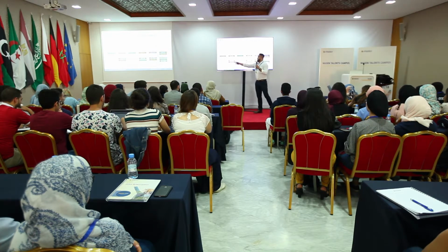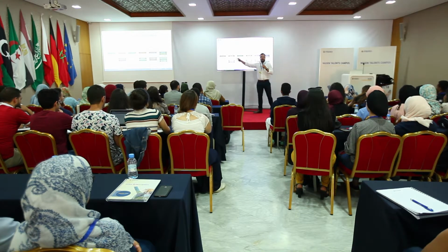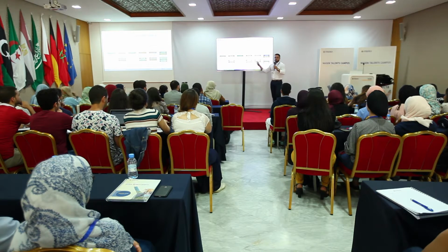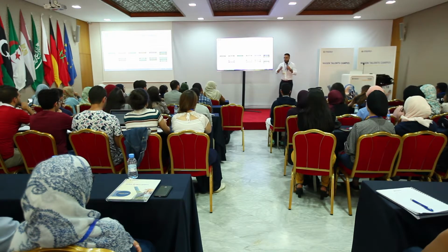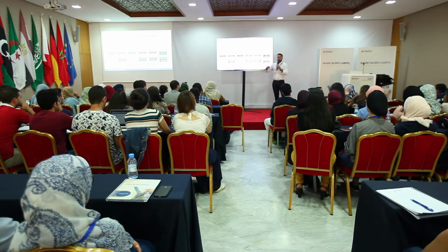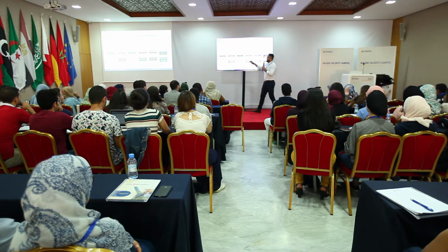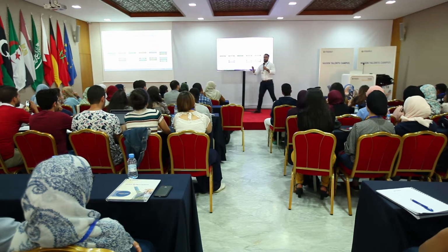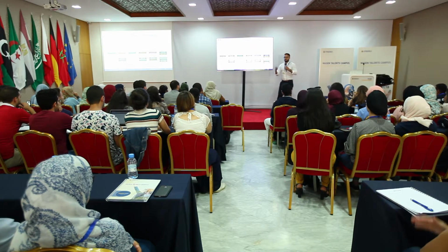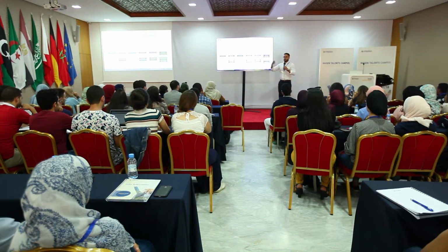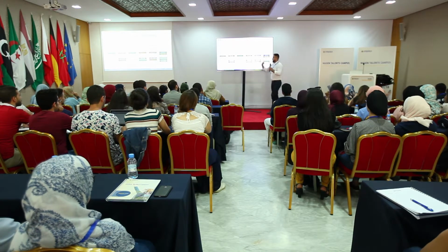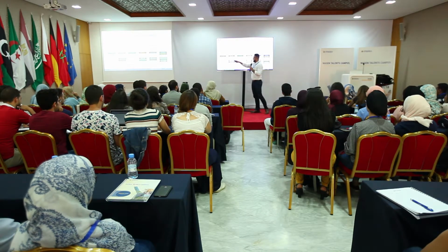because for a given location, for a given point of the day and of the year, say solar noon on the summer solstice, that gives me already the sun position, and I can read what the typical irradiation is. So solar noon on the 21st of June, this is my design condition. And for that, if I say I want to build a system that delivers 100 megawatt electric for that specific condition, I can size all of this, for a given size of heliostat, for a given size of receiver, etc.